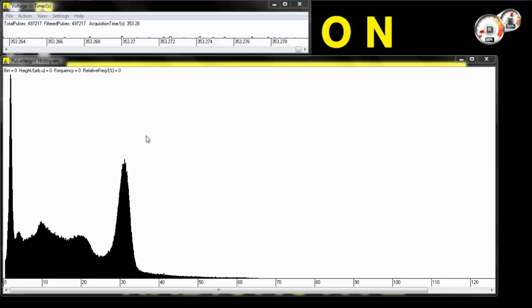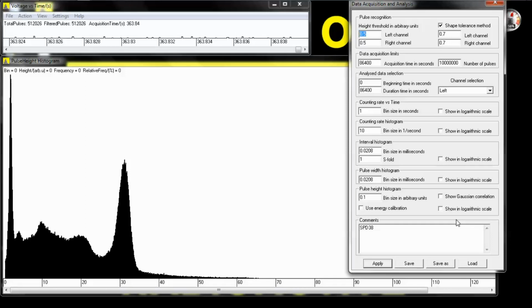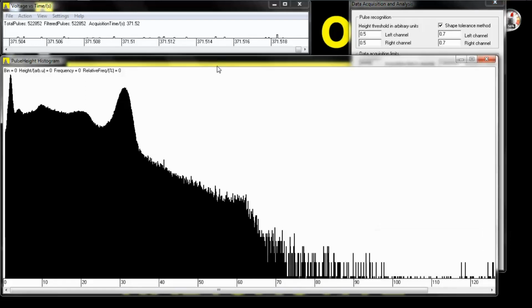All right, so we have a beautiful cesium-137 spectrum. Before we calibrate, let's go to data acquisition and analysis and quickly look at the logarithmic view and the bin size just to show you. Logarithmic view, click OK. As you can see, when in a logarithmic view, you're seeing a steadily increasing count size. So from here to here is maybe 1 to 10 counts. From here to here is maybe 100 to 1,000. From here to here is up to maybe 5,000 or 10,000, and so on. So it's a curvature going up, a logarithm.